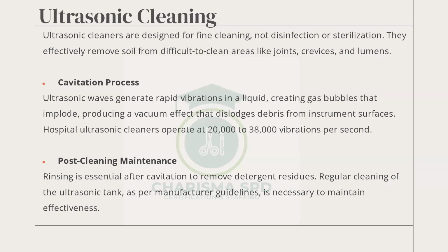So if you go to a place where you're going to have the ultrasonic, it means that every time you have to clean it as per the manufacturer guidelines, which is the IFU. So post-cleaning, keep it in mind, rinsing is essential after cavitation, okay? And then the cavitation is the process that the ultrasonic uses in cleaning. I'll go to the next slide.